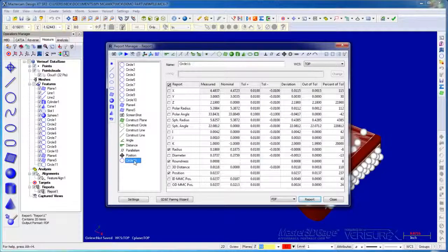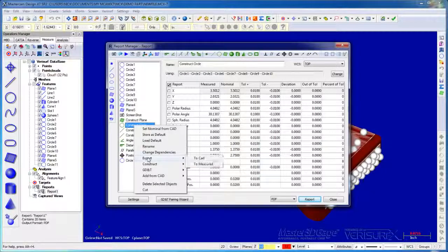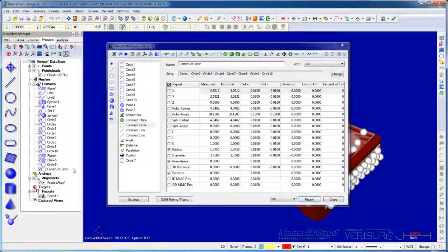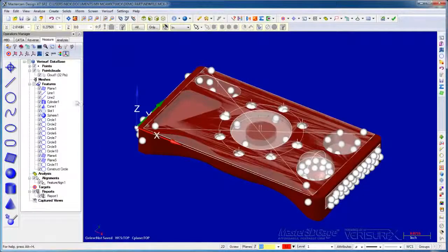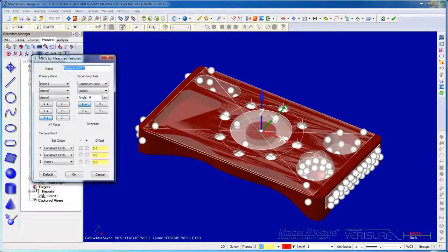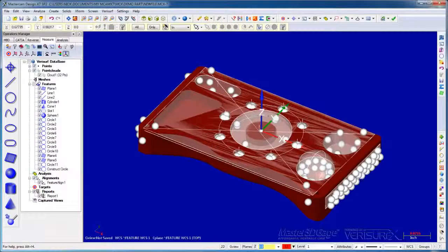Let's say our print requires that we report the hole pattern based on the top plane, the constructed circle, and circle 3. I'll take the constructed circle and export it to measured so it appears in the data tree. I'll run WCS from measured features. We use plane 1 to define the primary plane. The line from the constructed circle to circle 3 defines the axis, and the origin is set at the constructed circle center. When I choose OK, we see the WCS defined at the center of the hole pattern.